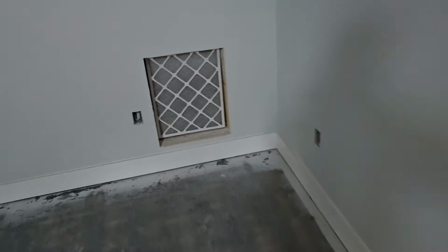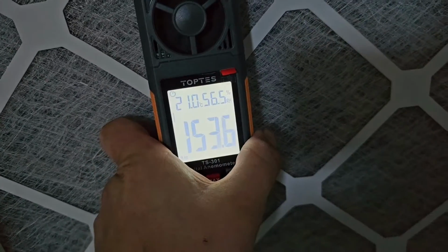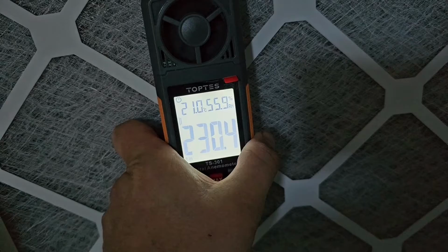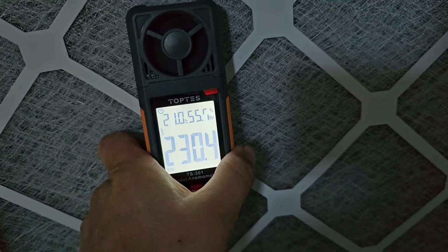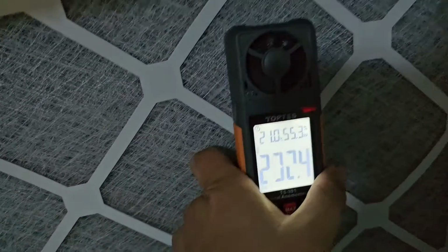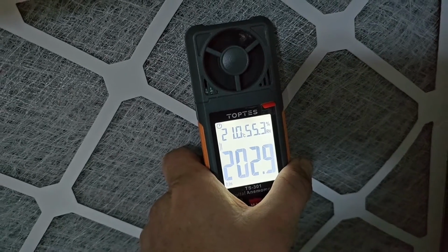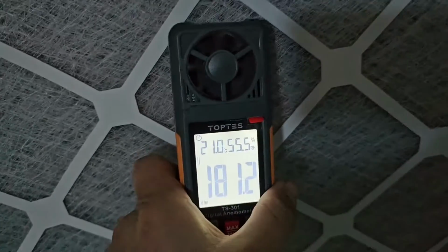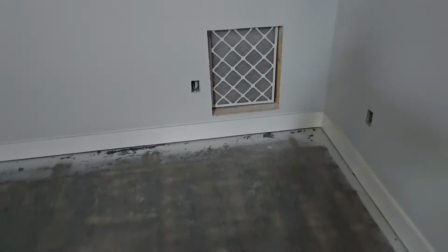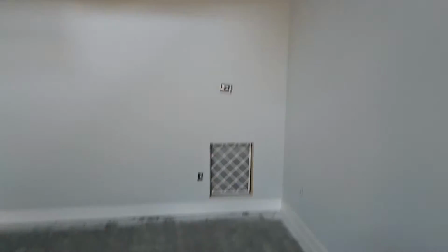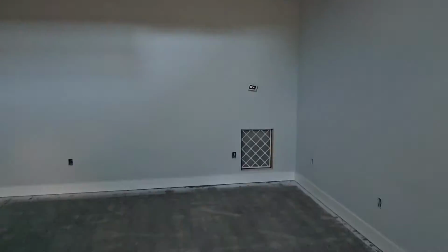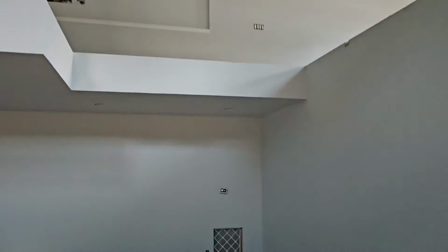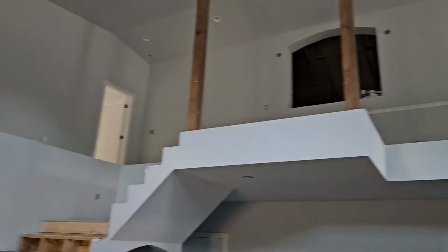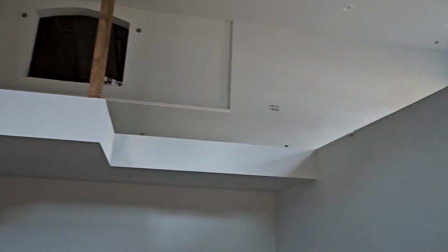Let's check out this return. Guarantee this one's a lot lower, probably. 100. Oh, 200. Still, I would like for them to be the same. You know, 200. I want at least 300, 350. No more than 500. So we can block off some of the return upstairs and get better pull down here. Curious to see what the comfort level is, although this is very open. So I like the fact that it's open.